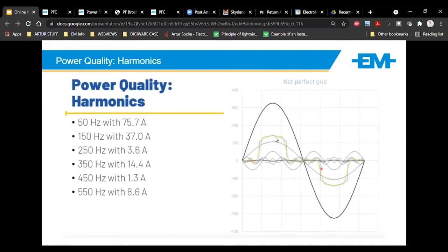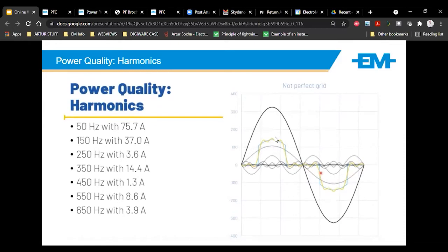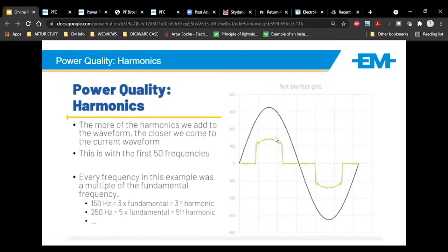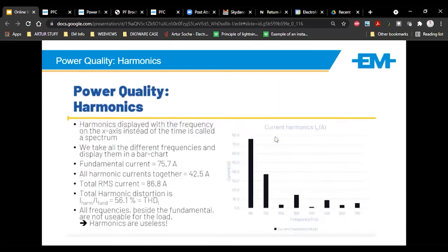So different steps in the firing of the VSD, on the gates or the rectifier, create this, let's call it, altered waveform out. So at the end, you're not left with the perfect waveform anymore. It's got a whole lot of distortion inside. And that distortion inside, that noise, is what we refer to as current harmonics.